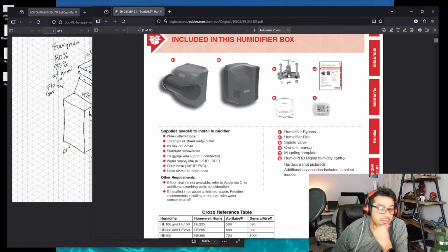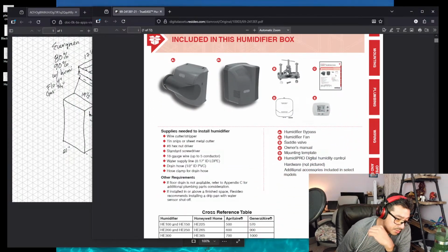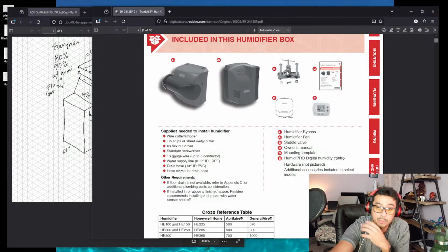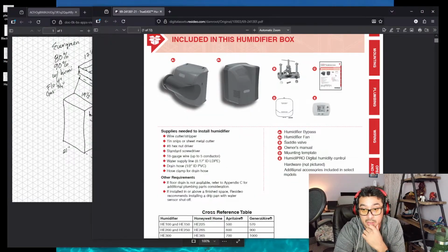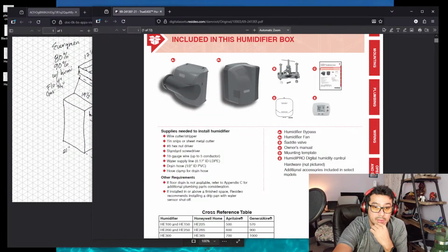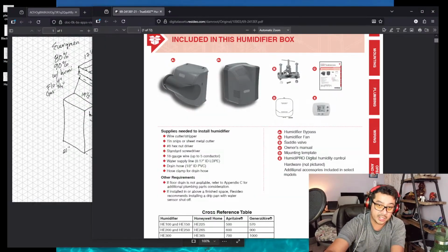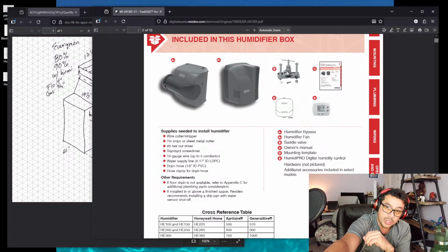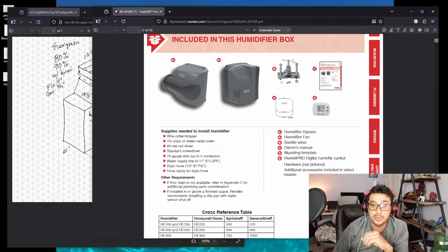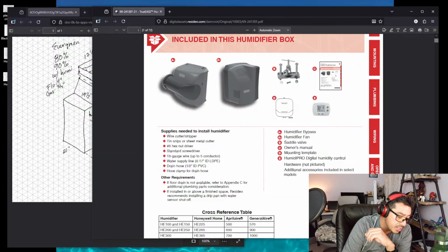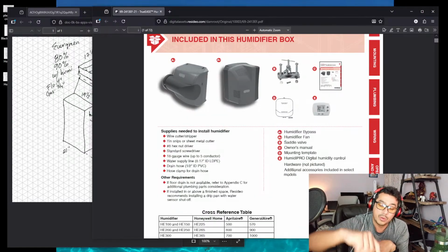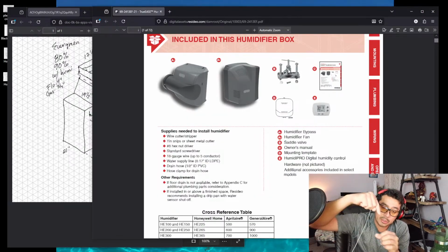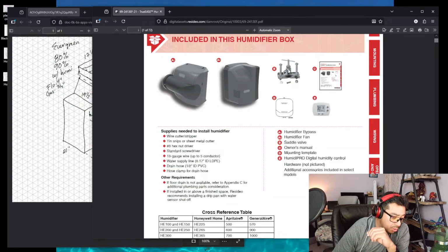So this is a needle valve. One thing I don't like about these needle valves is, I think they're called a piercing valve. Let's take a look. B&B saddle valve. So they're calling it a saddle valve, and it's a piercing valve. What it does is you set that on top of a pipe, and then once you start turning the valve, in this case it's opening it, as you're screwing it down, it's actually piercing into your pipe and making a hole in it.